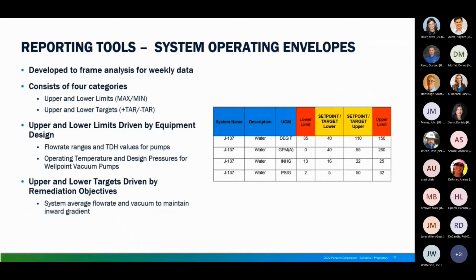The upper and lower limits, the excursions defined as max and min excursions, and upper and lower targets, the plus tar and minus tar. For the upper and lower design limits, these are all driven by equipment design, relating to operating temperature and design pressures for some of our vacuum pumps on the well point systems. It also incorporates any runout conditions or minimum flow rate requirements for any of our centrifugal pumps and what those corresponding flow rates and pressures are.